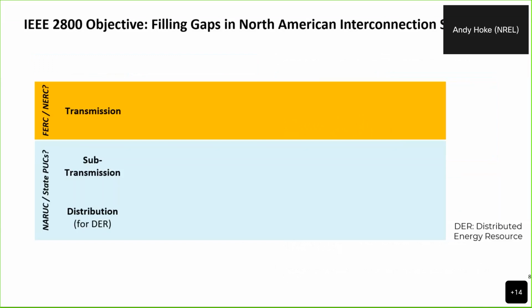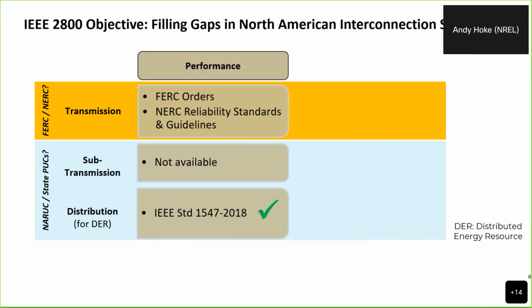Okay, so where does IEEE 2800 fit in the North American interconnection standards landscape? So we have had for quite some time IEEE 1547. It was recently updated. Well, not all that recently now anyway, in 2018. It applies to distribution connected resources, potentially some radial subtransmission connected resources as well, but is definitely not designed to apply to transmission connected or meshed subtransmission connected resources. In fact, its application in those environments has been maybe partly at fault for some of the different reliability events that have been occurring around the country recently. And so IEEE 2800 attempts to fill that gap by creating the first national interconnection performance standard for inverter-based resources connected to transmission and subtransmission.